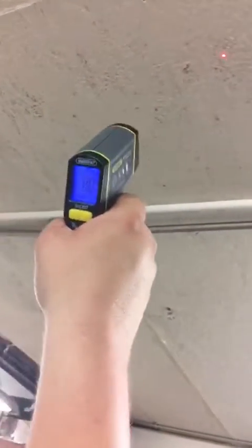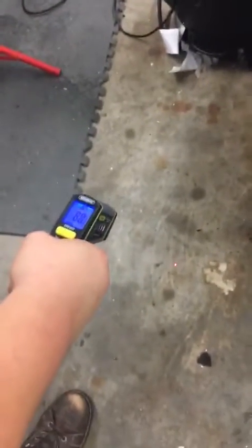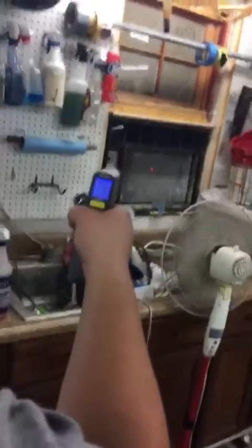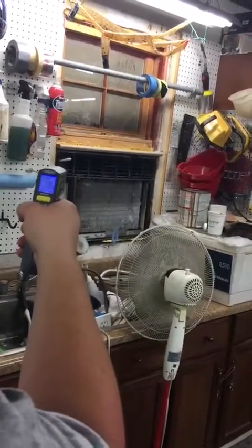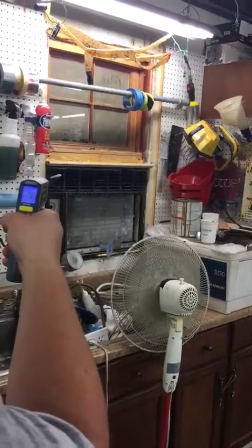For reference, ceiling temps are running around 80. Fans have been running for a few hours and air is pretty consistent in the shop — we're getting 81 on the floor, 81 on the walls, 81 on the ceiling. Air intake over here is coming off the coil around low 70s coming out up here.